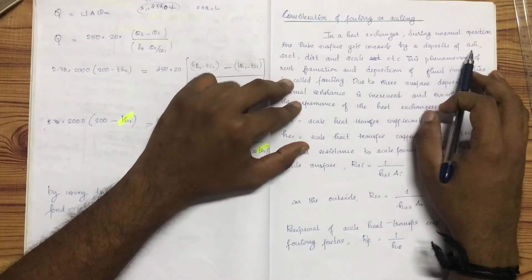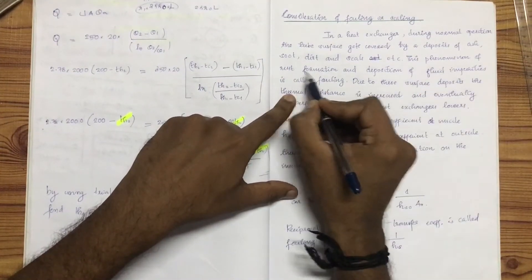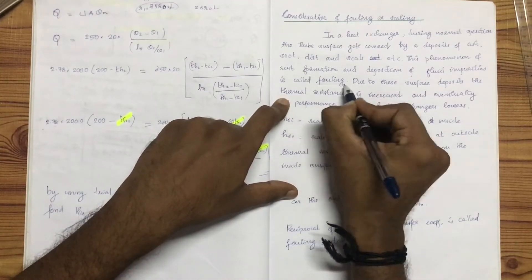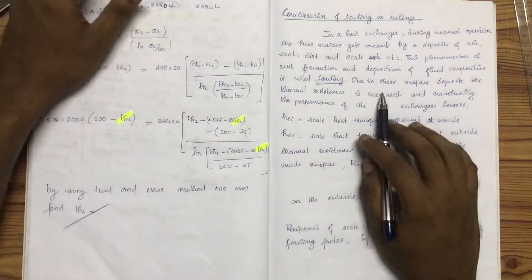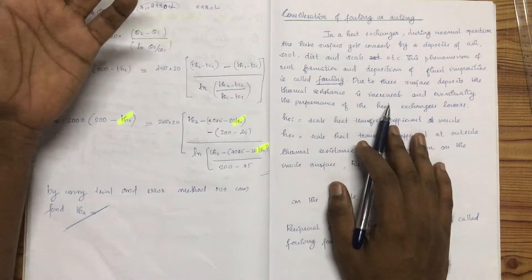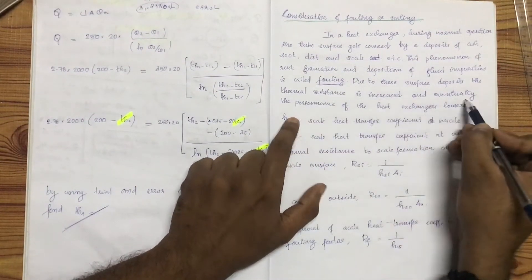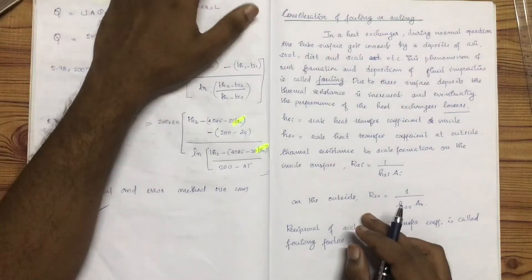When the heat exchanger is used, the tube surface gets covered by a deposit of ash, soot, dirt, scale, etc. This phenomenon of rust formation and deposition of fluid impurities is called fouling. Due to these surface deposits, the thermal resistance is increased and eventually the performance of heat exchangers lowers. Fouling lowers the performance of heat exchangers.